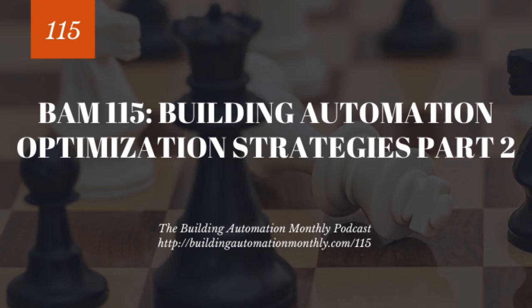Now, what does that mean? Well, take the humidity sensor, for example. That tends to be a 0 to 100% relative humidity range, which corresponds to a 0 to 10 volt DC signal. You would want to test this through that range. I'm not going to get into test procedures and test processes.